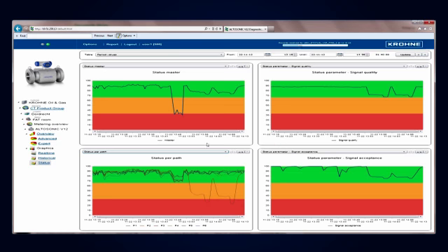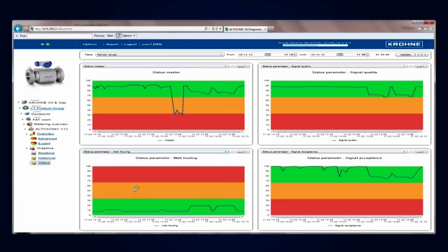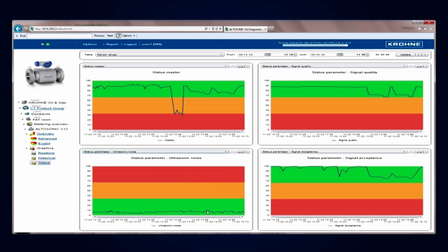So I can look a bit further. I can look at, for example, wall fouling. I click on wall fouling. Well, that doesn't really explain it. There's not much to see here. I could look at ultrasonic noise, for example. And again, ultrasonic noise, there has been very little. That doesn't explain the dip here either.